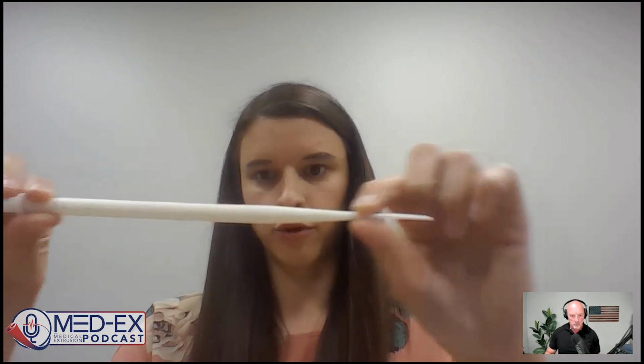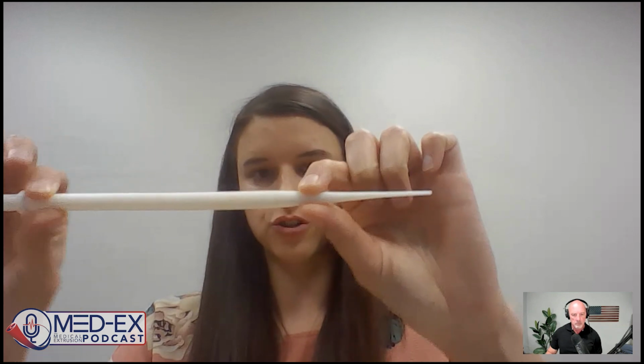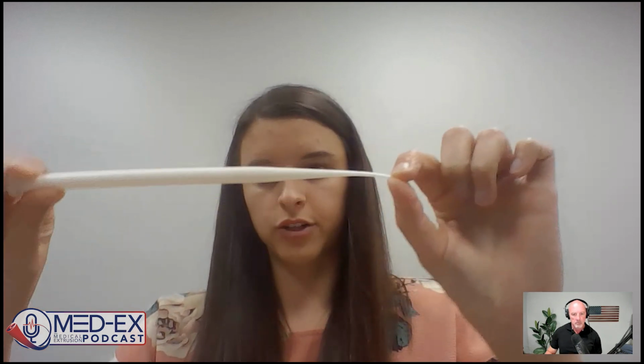I would say one of the biggest advantages that our equipment gives us is the length range we're able to accomplish with our tip forming machines. These tip lengths can be as short as extremely blunt tapered tips, even rounded full nose, bull nose tips, or they can be super long, tapered upwards of 3 inches long. Here you can see a really long one. This is a PVC dilator extrusion that has a 3-inch long tip.